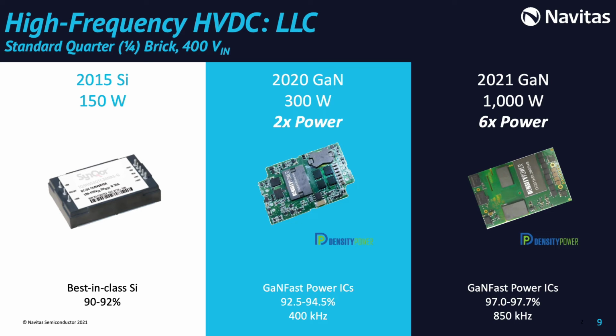In some data center and industrial applications, we have a 400-volt DC bus and need to convert to lower voltages. Here we see the progression in the standard quarter brick form factor from silicon to hard switch GaN and then soft switched GaN Power IC applications, all the time increasing frequency, efficiency, and power density. Now up to 6 times more power in the same quarter brick form factor than the original silicon design.